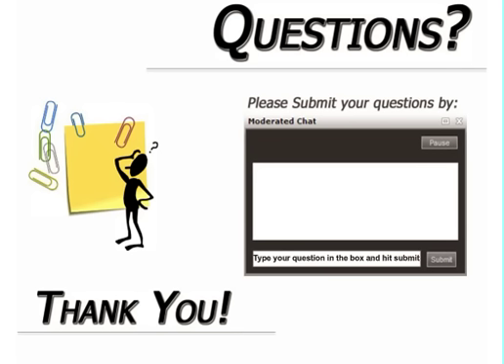All right, Sean, we have time for just one more question. This one's from Chuck. How do you design for muddy bottoms? Is not the ground temperature higher than 39 degrees? Well, the issue with the muddy bottom is that the heat exchanger will actually disappear into the mud. You don't have enough piping. It's like a ground loop then. Rule of thumb, as I showed on that slide, roughly 300 lineal feet per ton, sometimes 400, somewhere in that neighborhood, for pond loops. Well, that same ground loop length would probably be double that, maybe more. And if you drop into the muddy bottom, you don't have enough heat exchange, you're going to have a terrific struggle trying to meet capacity for that structure.